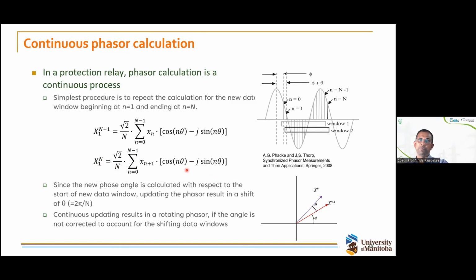Now, what happens is that when we shift the window, we always start our reference cosine and sine function at the beginning of the data window, or the first sample in that particular window. Which means we are basically shifting our reference at each new calculation. Therefore, when you look at the phase angles, even if the magnitude is constant in the measured signal, you will see the phase shifting by a certain angle, and that angle is equal to this theta, because that is the angle corresponding to one sampling interval. Because you are shifting your cosine and sine reference signals, you will see the phase angle always changing from one time step to the next.